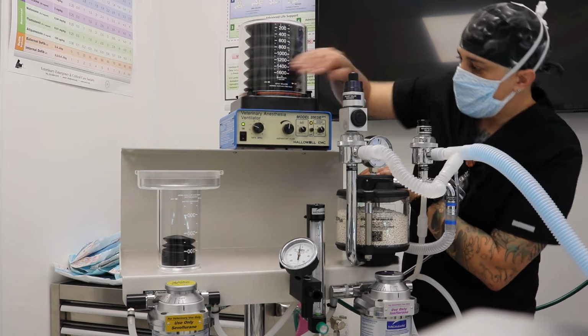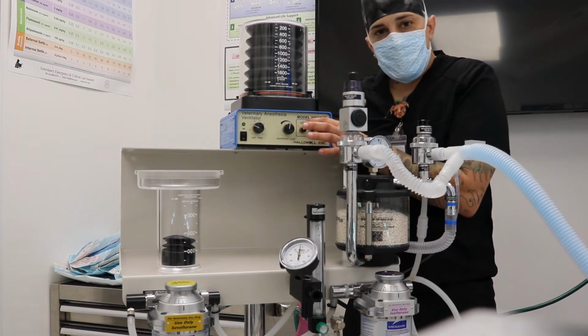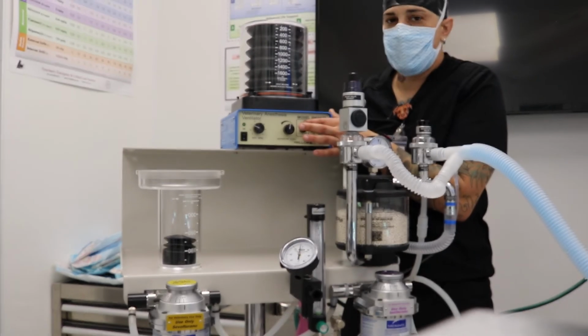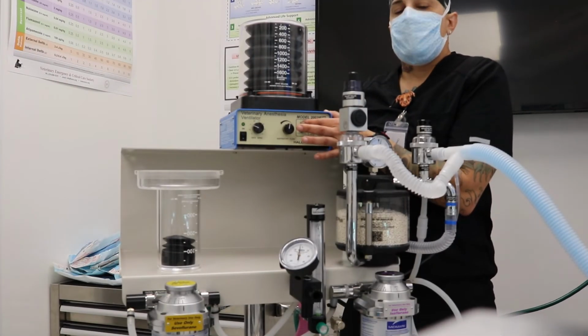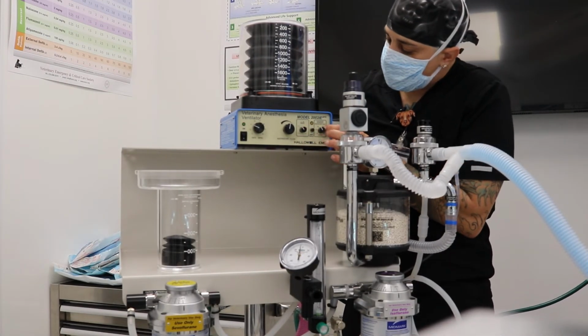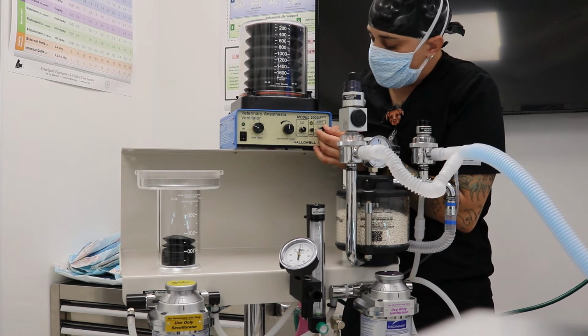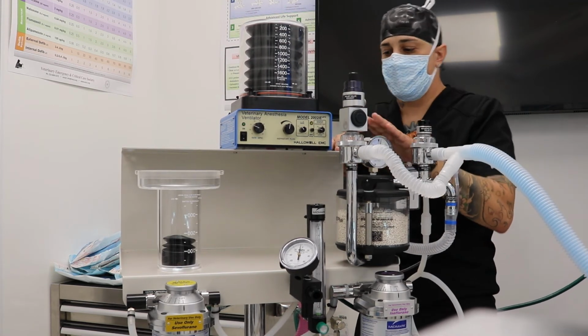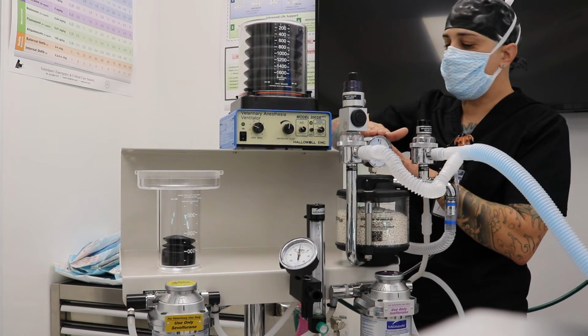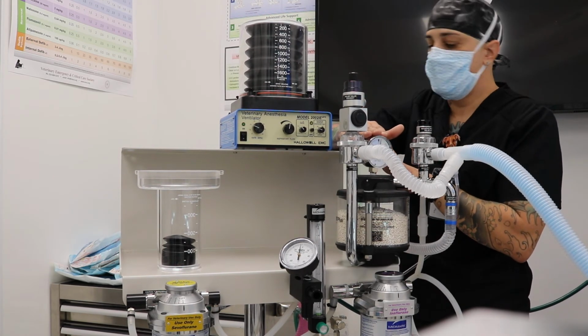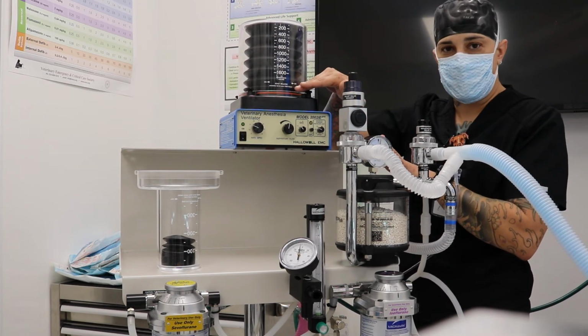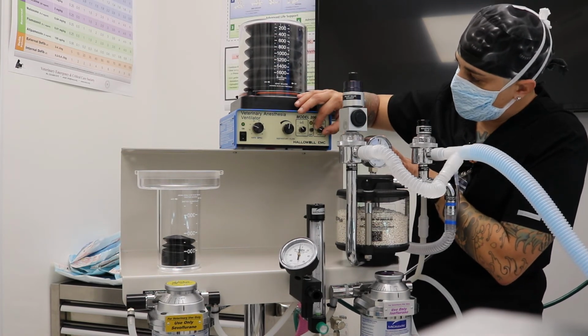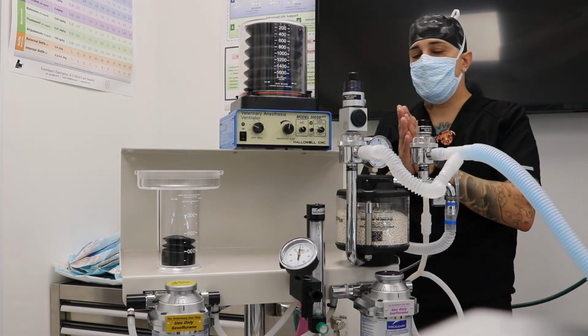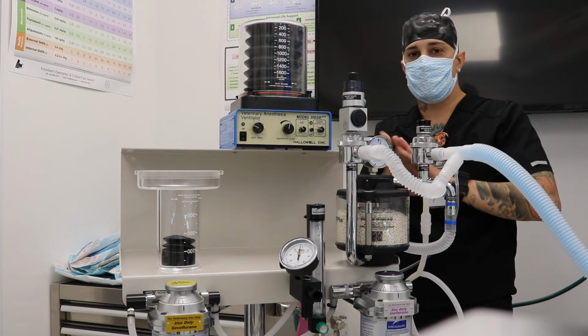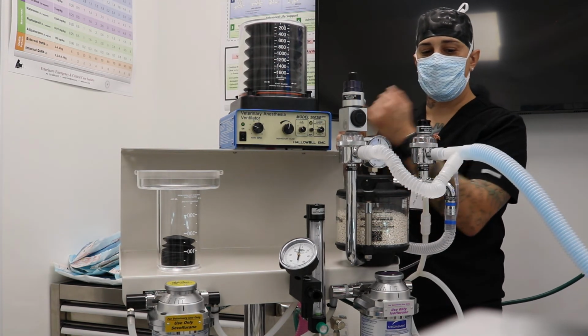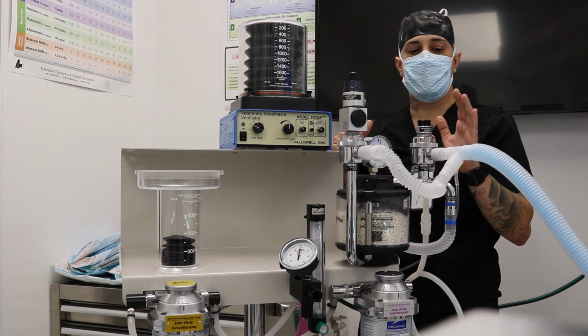Now, your inspiratory-expiratory ratio is here, 1 to 2. 1 breath for an inhale, 2 for exhale, 1 to 2. I'm going to drop this back down to 20, because like I said, this correlates with my manometer. This will tell my machine that if I go over 20 centimeters of water with the breath, it's going to beep at me like it did. So now that's back down to where we need it. So those are your leak checks. That's how to troubleshoot. Those are the 2 sounds you'll hear if your maximum working pressure limit is over and if you don't have your pressure transducer on there correctly.